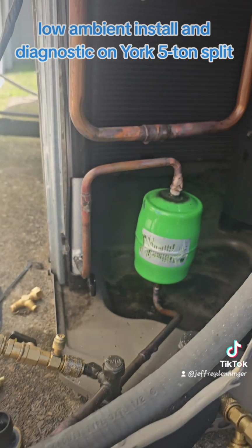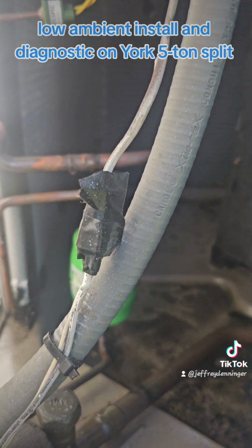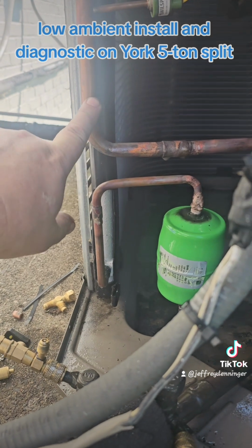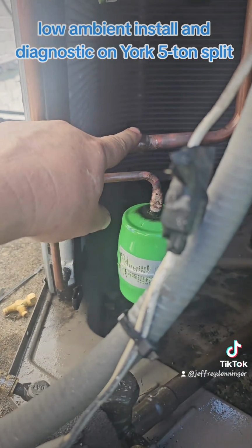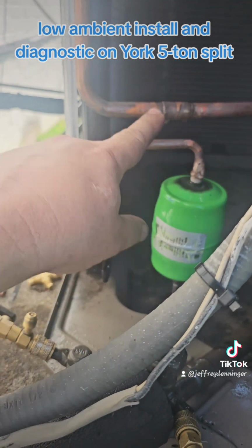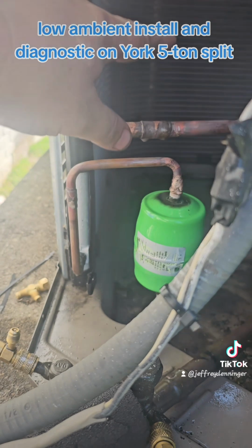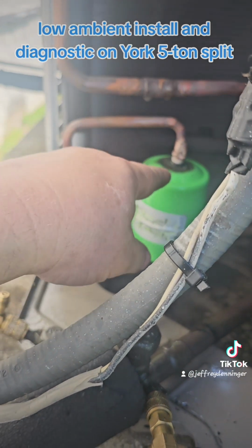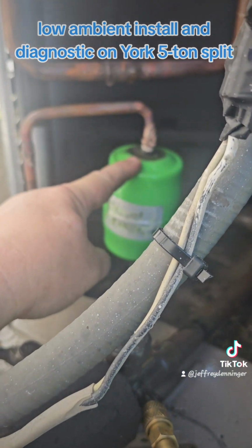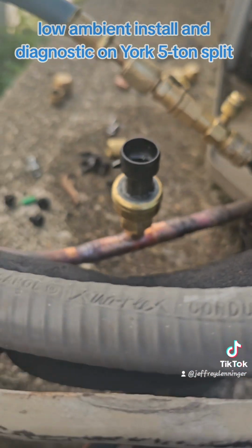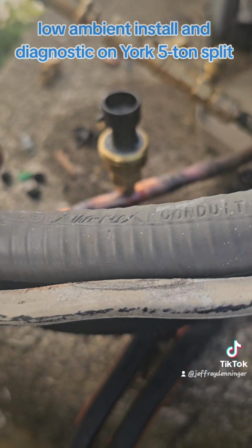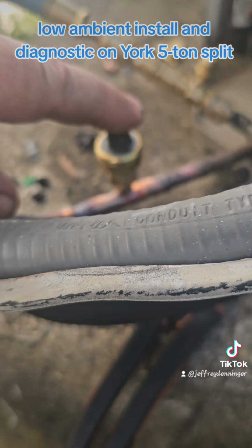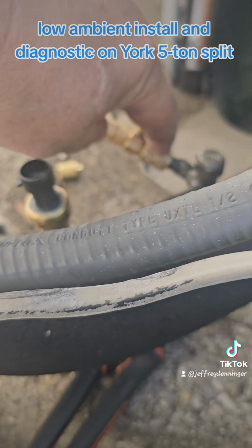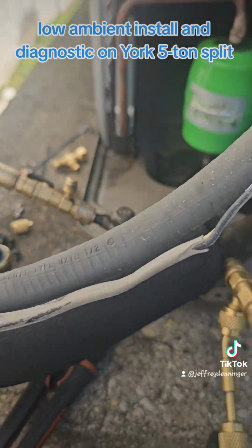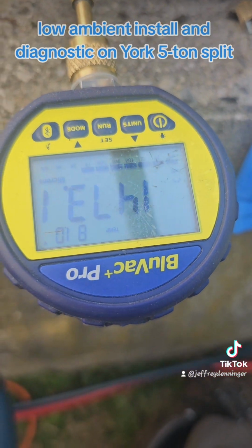Okay, back at it again this morning. We determined that we had a restriction somewhere in here. So I cut the line here, removed the dryer, flushed it with nitrogen, got out whatever was in here. There was a little bit of oil. Put a new bigger dryer on, properly sized. I also put an access port here for our low ambient pressure transducer instead of doing a T off of here, which will leak. Right now we're in a vacuum and we still got a little ways to go.